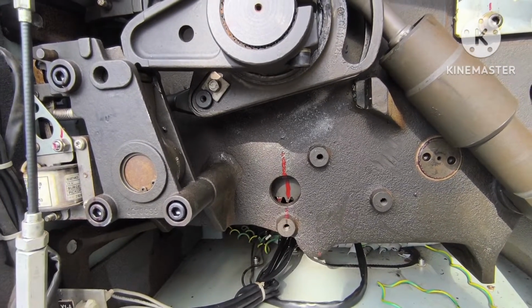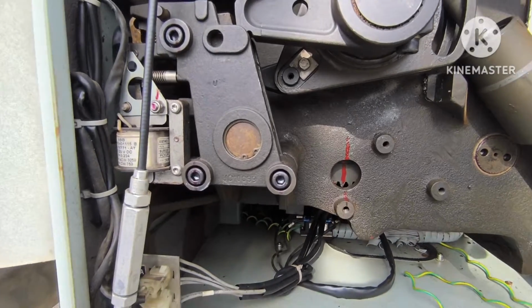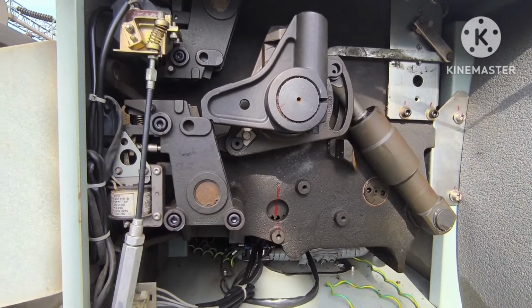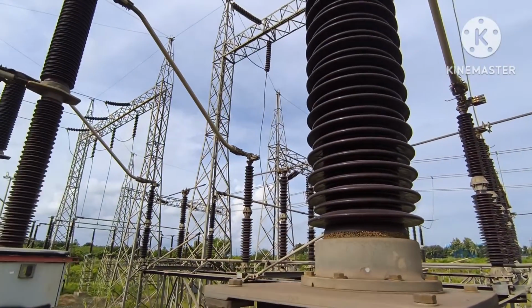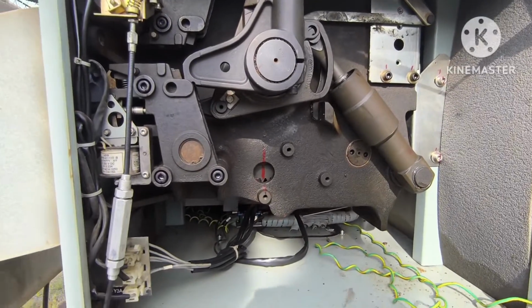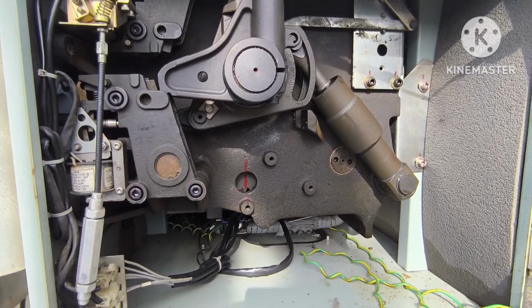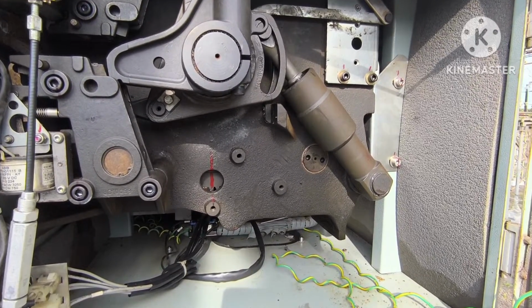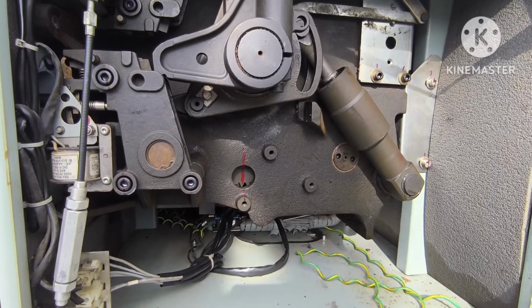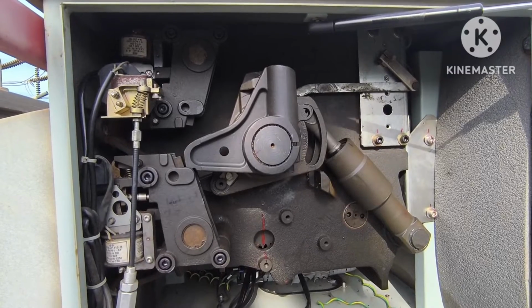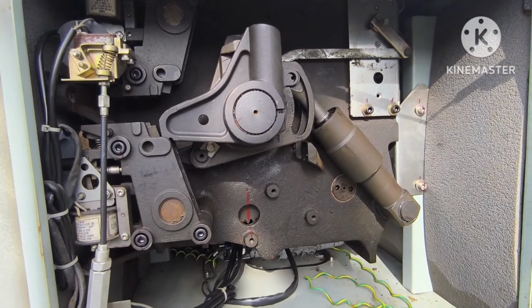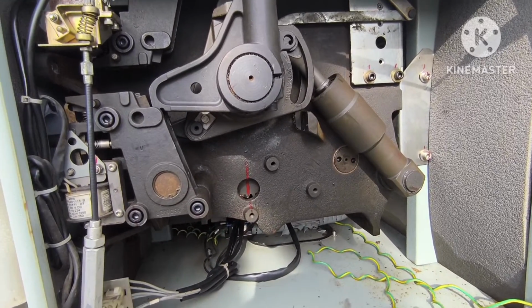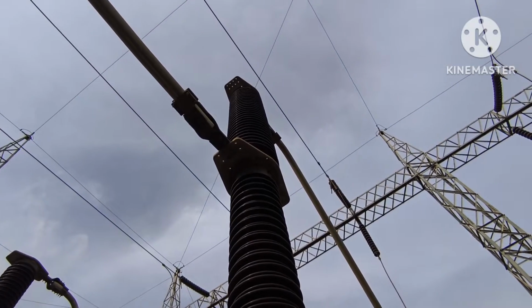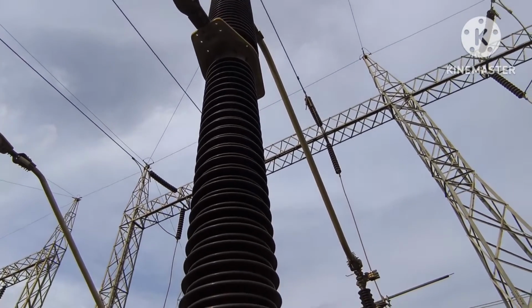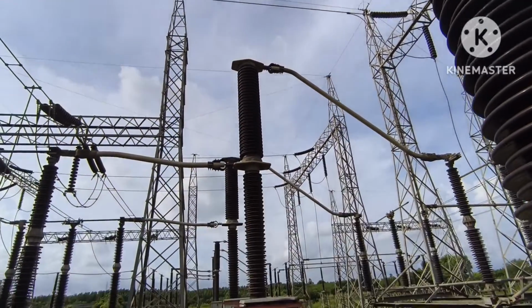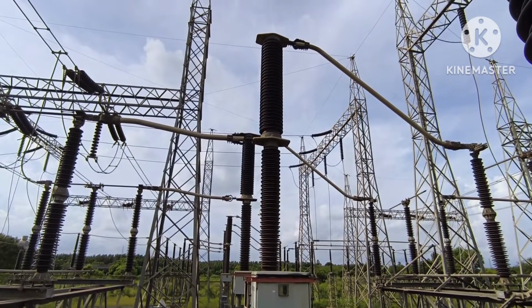For this type of breaker, maintenance generally requires visual inspection every 1 to 2 years. At every shutdown we have to do physical inspections, and lubrication is required after 2000 mechanical on-off operations, and preventive maintenance is required after 5000 mechanical on-off operations. Overhauling is required after 30 years or nearly 10,000 mechanical on-off operations. This is the maintenance. So normally whenever there is a shutdown opportunity, we have to check the tightness of the middle pad and top pad nuts and bolts, and clean the bushings. Normally we have to do this. Otherwise it is mostly maintenance free.